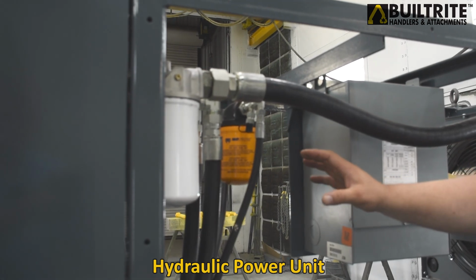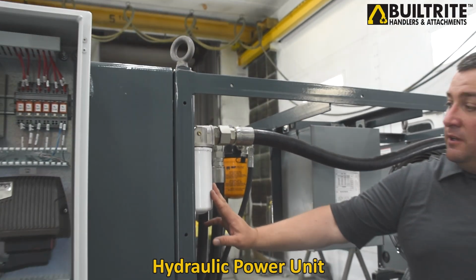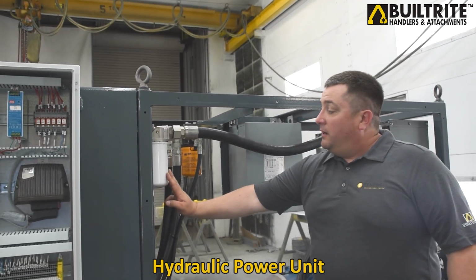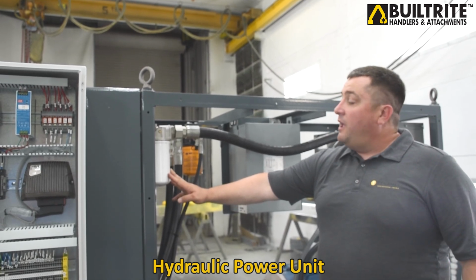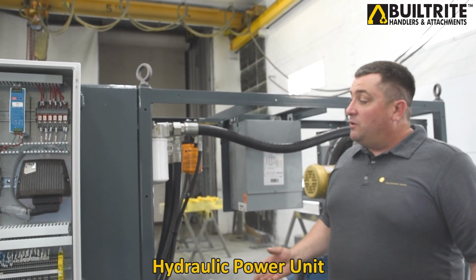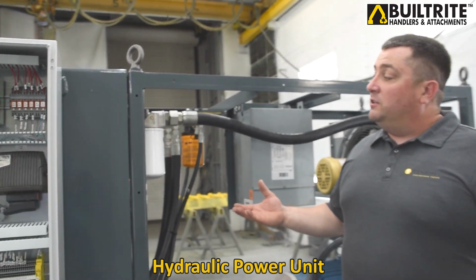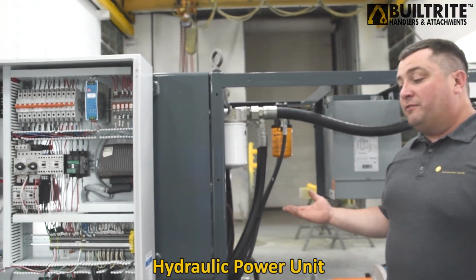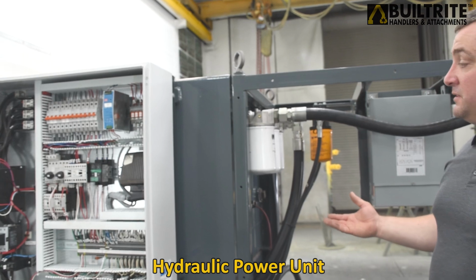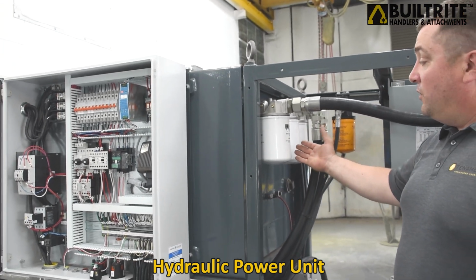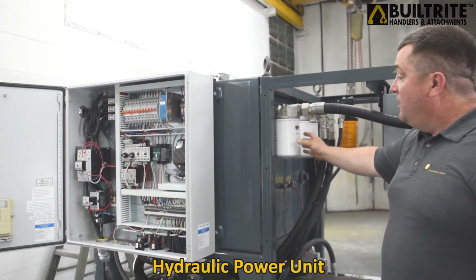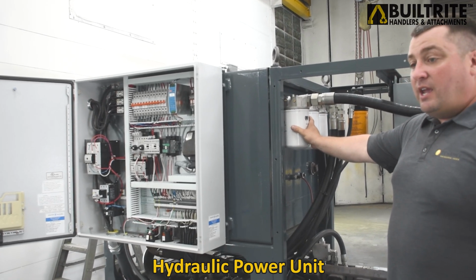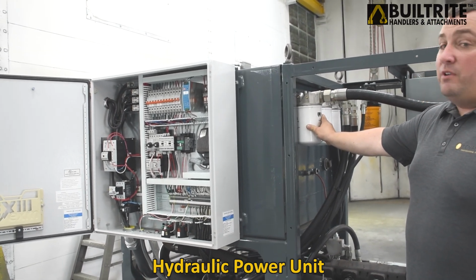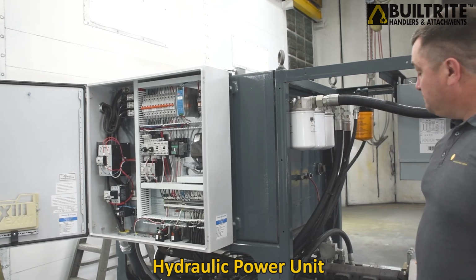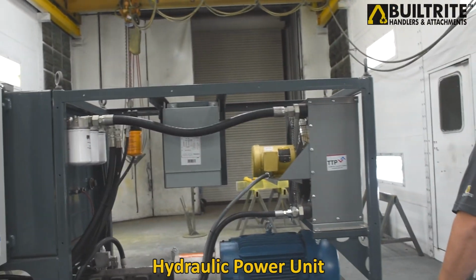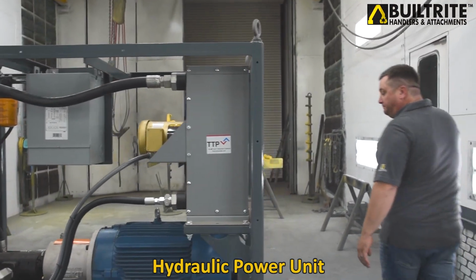We recommend that for your return filters that you do oil sampling every 1,000 hours or quarterly. That'll tell you how often you need to change your filters. If your company does not do oil sampling, we recommend that you change your filters every 1,500 hours. We'll move around to the other side of the power unit.